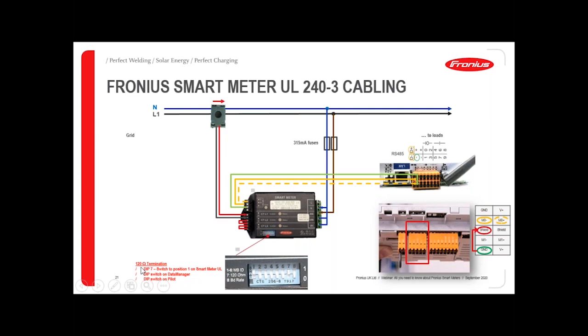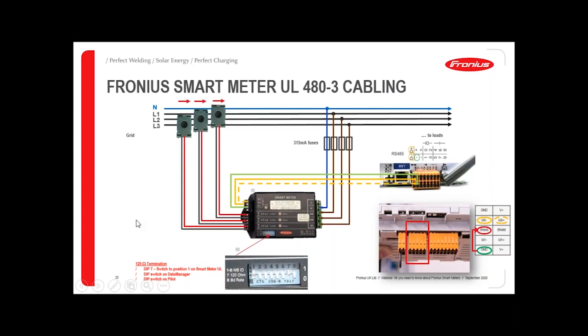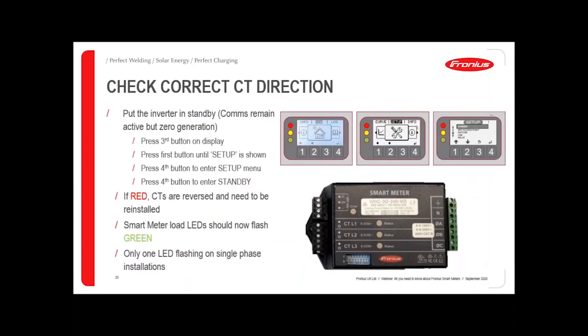We have very similar connections for the data here — D plus, D minus, and ground going across to the data manager and to the Gen24. The termination resistor on the Smart Meter UL is set by putting DIP switch number seven into the upright position, so just make sure that this is always in the upright position. For the three-phase installation, we have a very similar setup, but now we have the second and third CTs. We have phase two and phase three connected. Make sure that the termination resistor is in the upright position and that you've connected at the data manager or the Gen24.